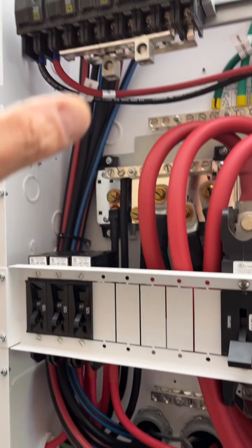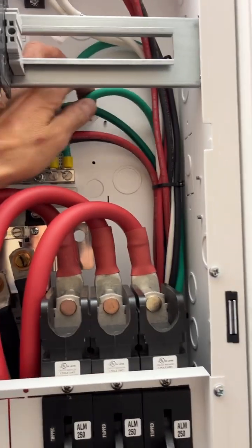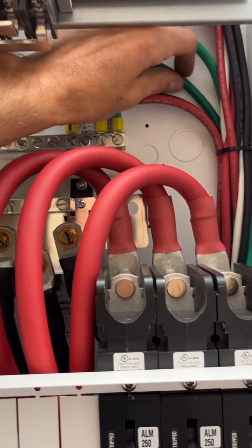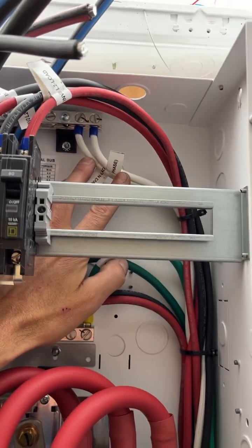Then through the 50-pound zip tie, I went through this earlier on another video just to secure this up out of the way so this wouldn't drop. Always leave a nice little bit of slack so nothing's too tight. I'm not pulling on this, I know it looks like it but it's actually pretty loose there. This one's zip-tied up, my neutrals are zip-tied up all the way along. Again, I only have two neutrals because only the load outputs get the neutrals. The grid-tied does not. It only runs the 120-240, and then yeah, all the way down. Working in behind here, it's a little bit challenging.